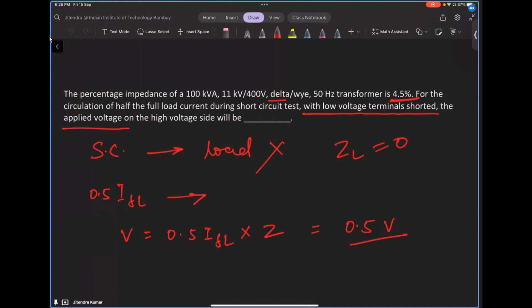If you don't know the per unit concept, what you would do is compute everything in actual values, refer to the primary side, and calculate again. But if you know that half the full load current is flowing, the same current in per unit will flow on the primary side as well. So I can simply write it as...